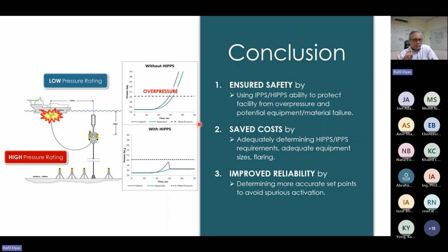One is, what is the safety time? How long do I have in order for this valve to react? And another thing that we determined is what is the accurate set point. Because if we put the set point too low, you might get spurious trips in the system.